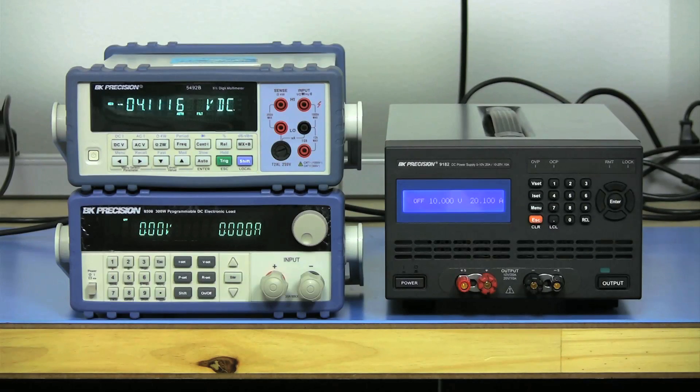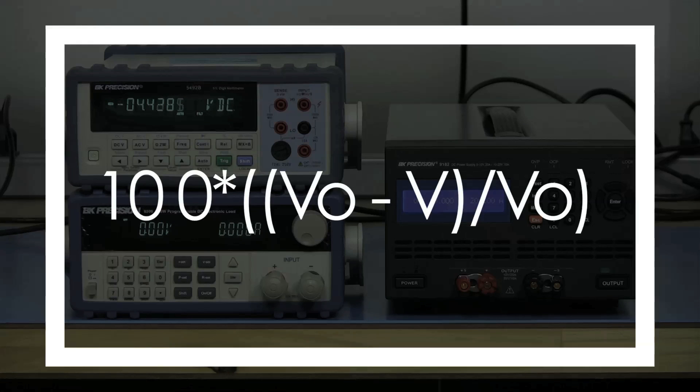Now the load regulation can be calculated in a percentage by the following formula, where VO is the voltage with zero current load, and V is the voltage you just recorded with 20 amp load.